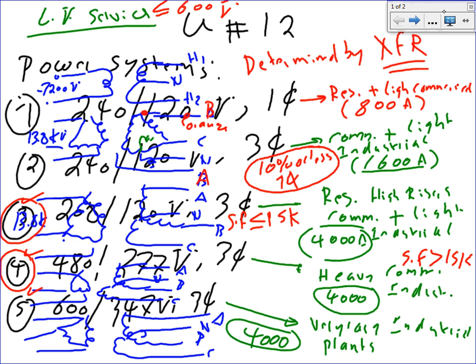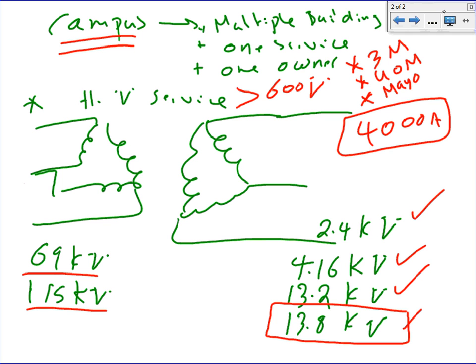See what I did here? Here's my feeder coming in. If your service is any one of these, Y or delta Y, meaning neutral, you tie this to Mother Earth. You establish your neutral, and you pull. Oh, so it could go delta, and then you can pull a Y in on. Absolutely, no problem. Yes. It's a delta here. Let's say we move another mile, there's another delta, so these are coming here to another transformer, and from this transformer, I have a Y.